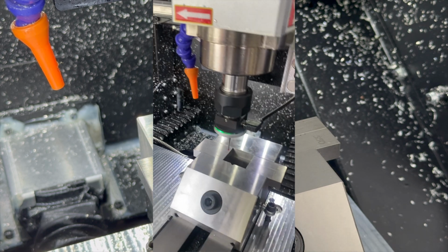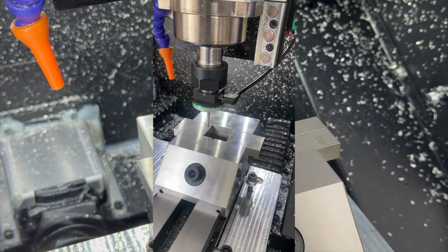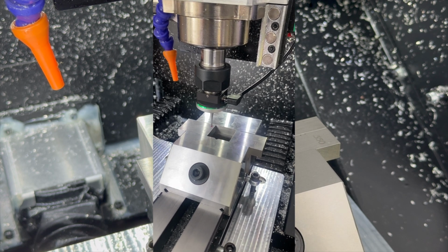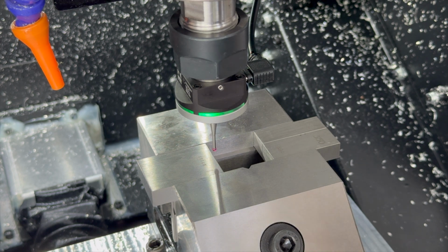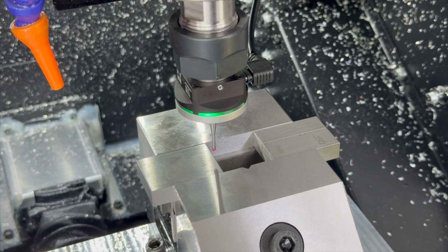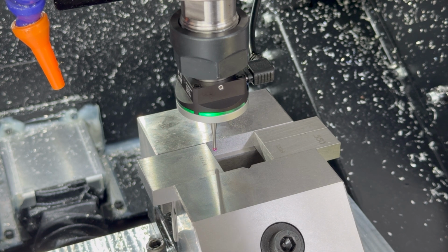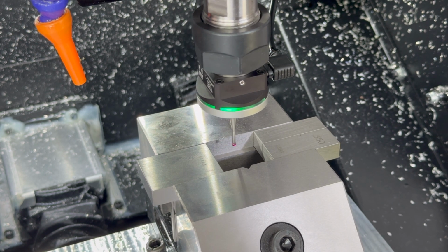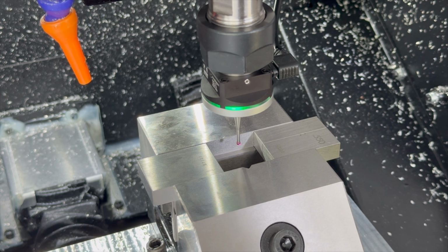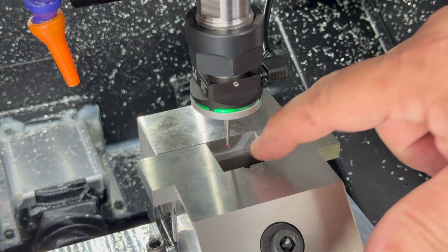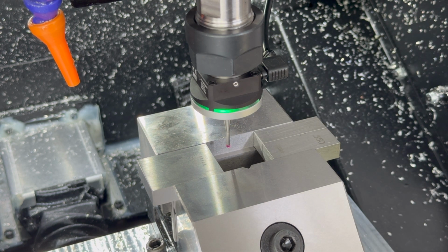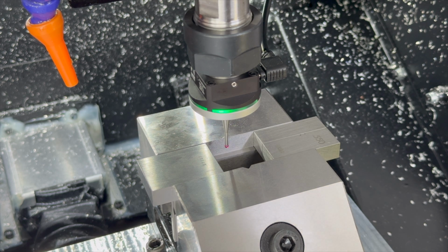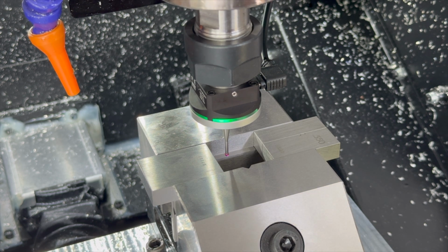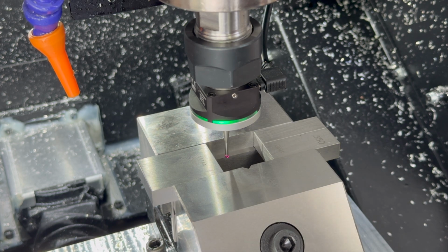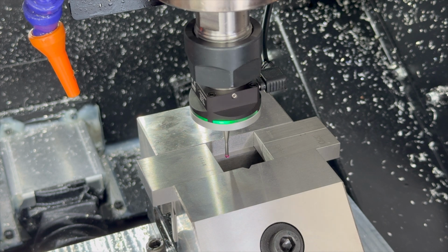And what we need to do, we need to put the stylus in the center of the square, and I'll do that in just a second. Alright, we're putting the stylus in the center. Let's see, we gotta move X just about right there. Actually, I want to be a little bit off to the side. I don't want to catch these knots here when I do the front to back Y measurement. And let's drop it in. That's probably good enough. All right, very well. We have the probe inside the 1 inch square.